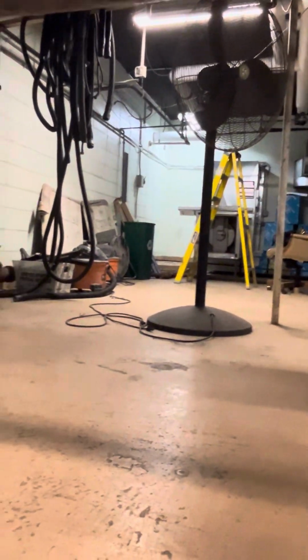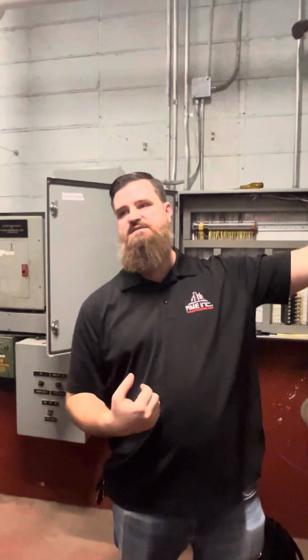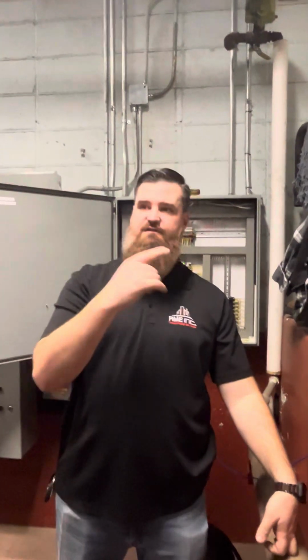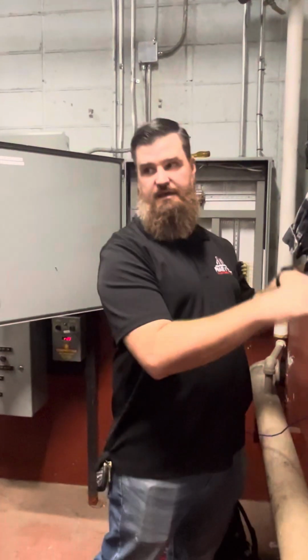The reason we need status for that is to turn on that combustion air fan that's over there, okay? If boiler 2 turns on, that fan gets turned on. Otherwise, we have to turn that fan on, wait for status, confirm that the outside air damper is open, and then we'll enable those boilers over there. So, in case they want to run the boilers in manual mode, we wanted an override button so that we could still run the fan and then run them in manual mode. You could still override the fan command on and everything else, but at that point, if you're going to turn these boilers on manually from here or from over there, you are now putting the whole system into manual mode, and you need to operate things as if you were in manual mode, okay?